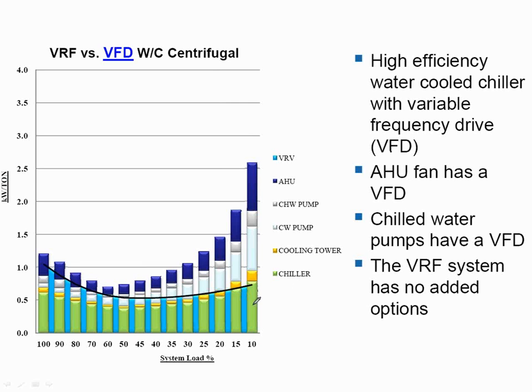Now when I look at my chillers in green, right? So if I look over here at a 100% loaded chiller, he's using 0.6 kW per ton. My VRF is using 0.9. My chiller is more efficient than my VRF system, right? And that's true for most of these cases. Green is lower than baby blue all the way until I get down to here to this 10-15% range, and then the VRF beats the chiller, right?